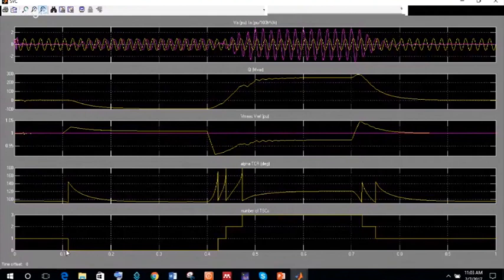And here it is the number of thyristor switched capacitors. Since voltage is increased, we do not require capacitors in the circuit. So capacitors are out, or they are not connected. It is the reactor which is only controlling the voltage. So how does it control voltage? By absorbing the reactive power. This reactive power is negative, which is being absorbed by the thyristor controlled reactor.